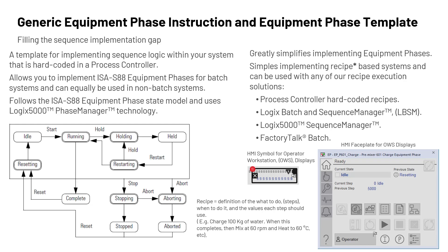It follows the ISA S88 equipment phase state model and uses Logix 5000 phase manager technology. An example of the ISA S88 equipment phase state model can be seen in the diagram on the left. It greatly simplifies implementing equipment phases and also simplifies implementing recipe-based systems that can be used with any of our recipe execution solutions — for example, process controller hard-coded recipes, Logix Batch, Sequence Manager, and our FactoryTalk Batch comprehensive batch management solution.